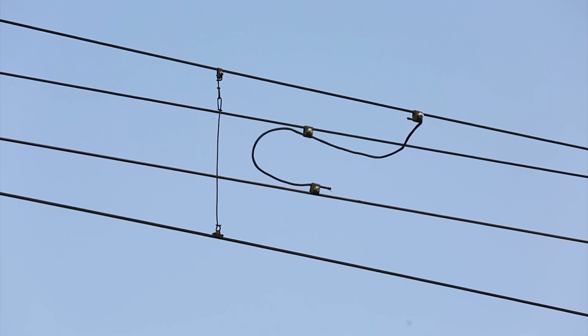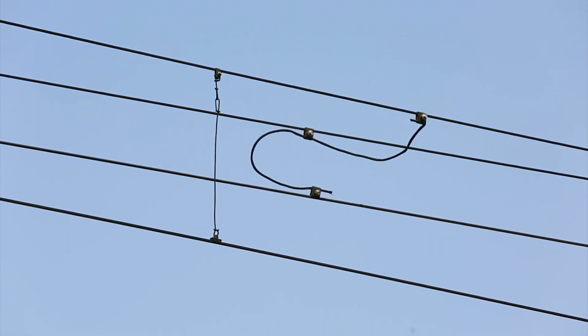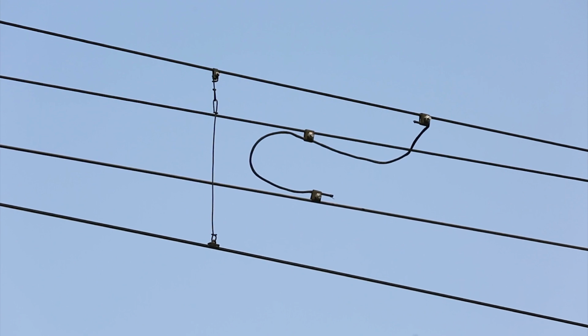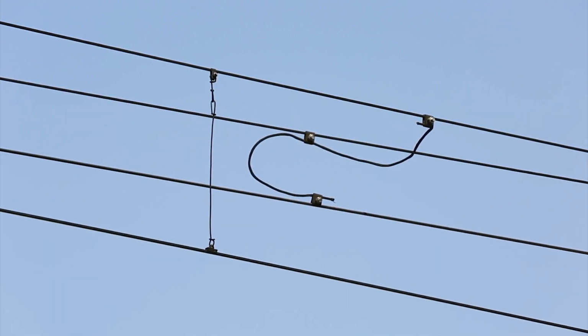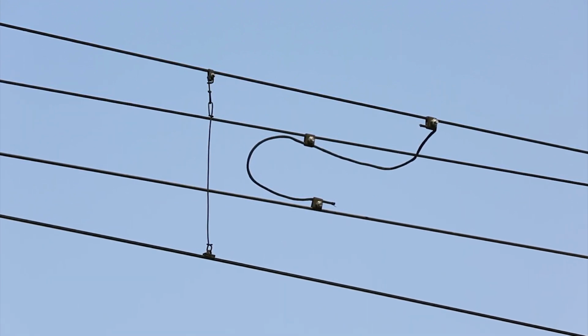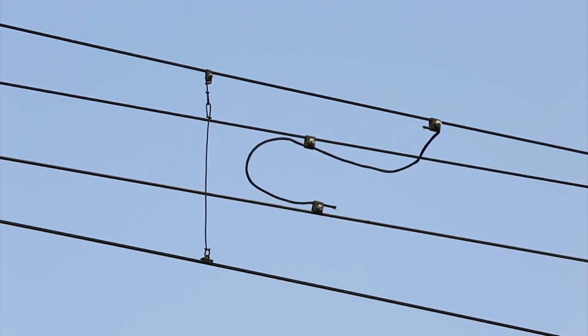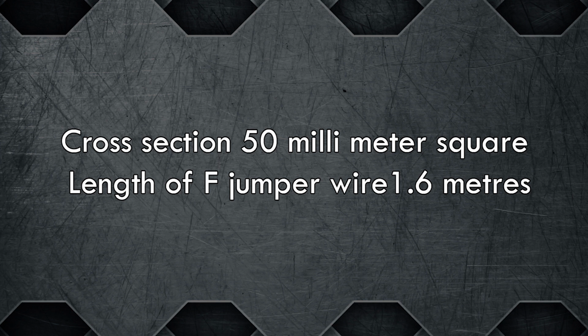F-jumper, also known as potential equalizing jumper. F-jumpers are provided at insulated overlaps to balance the potential between in-run live OHE and out-of-run dead OHE. Cross-section: 50 mm square. Length of F-jumper wire: 1.6 meters.